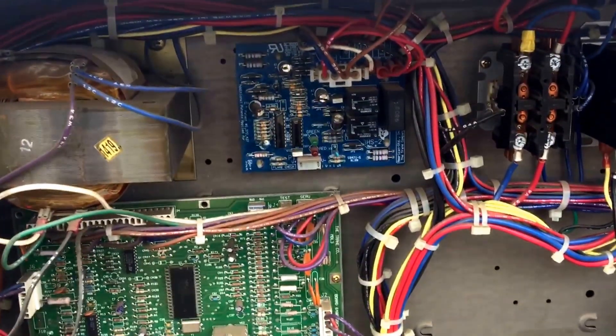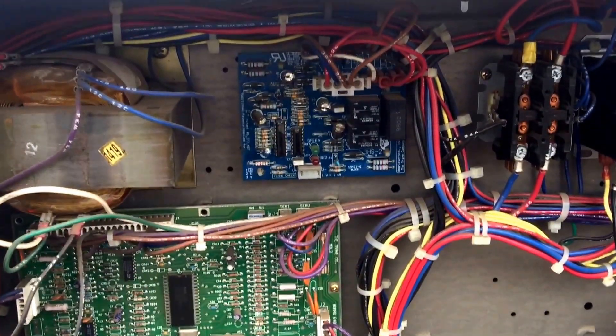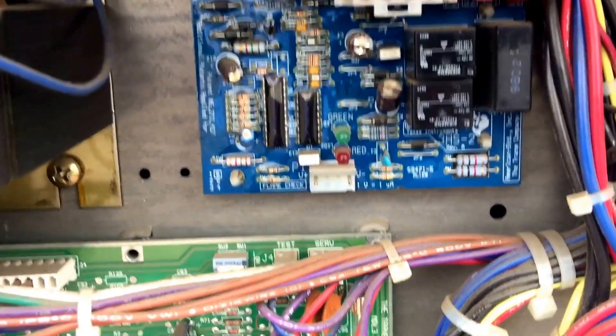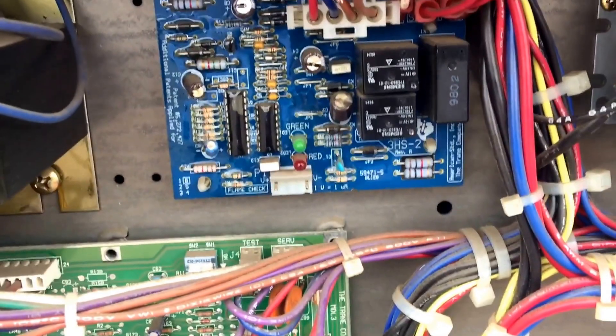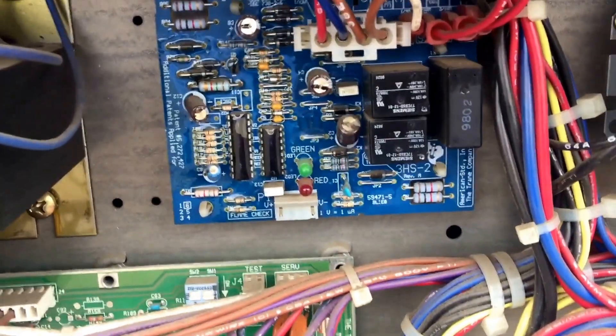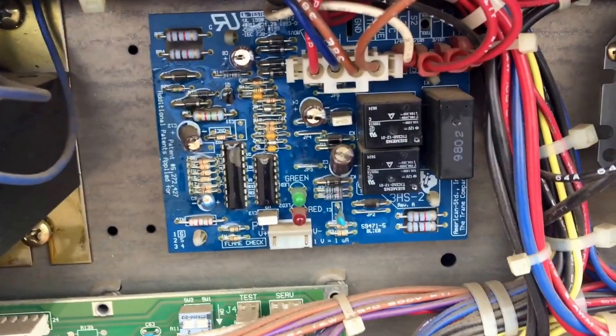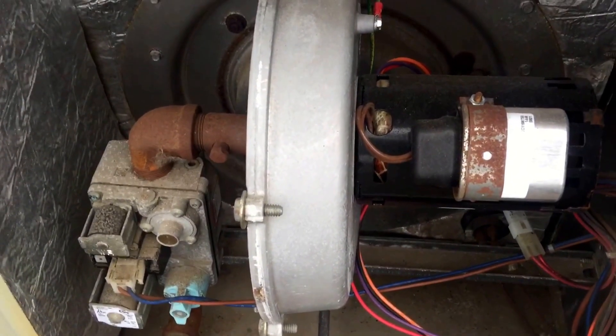First is the ignition module. You can watch this — once it goes into heat, I'm sure most of you have noticed the lights come on the module. It tells you that the unit is calling for heat. Okay, now we've got a blinking. That motor is starting.